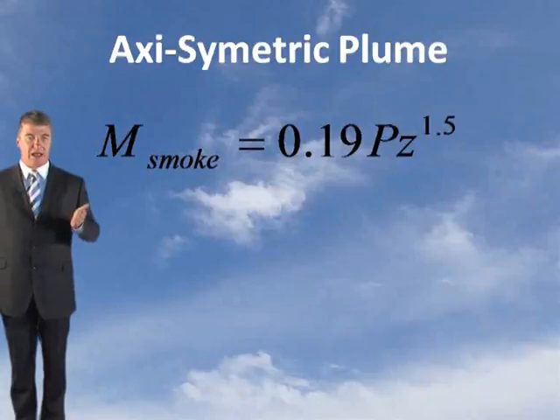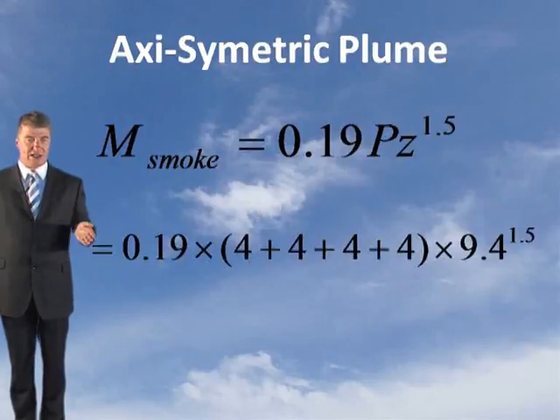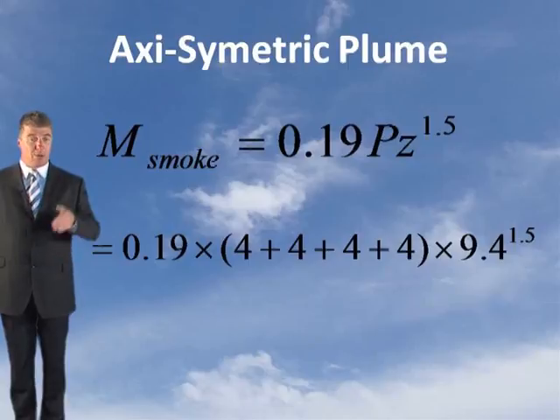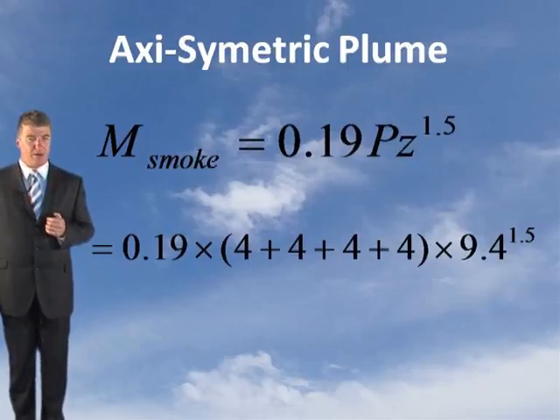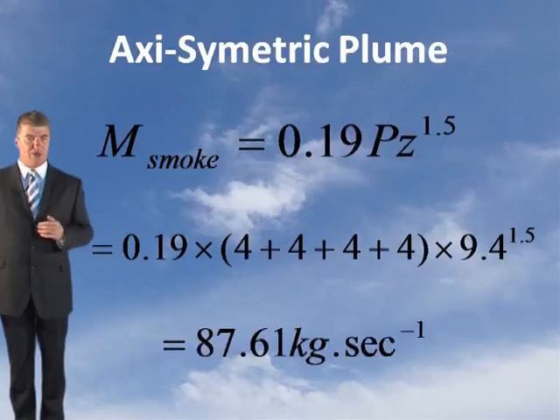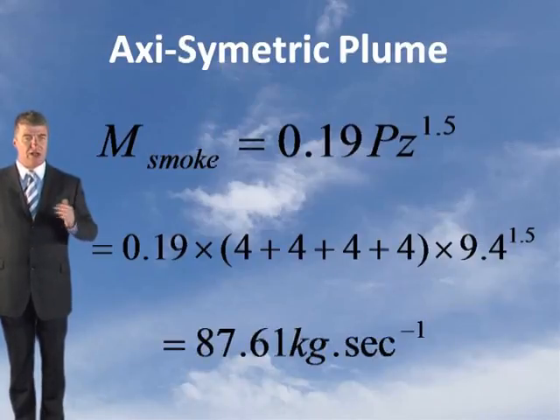So M_smoke equals 0.19 times the perimeter — which is 4 plus 4 plus 4 plus 4 — multiplied by the clear layer height of 9.4 to the power of 1.5. This gives you 87.61 kilograms per second.